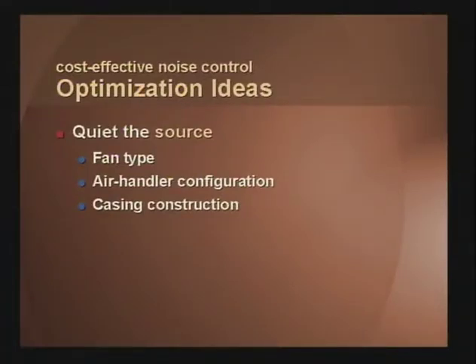Let's take a look now briefly at the source. The source is the air handler. What can you do there? Well, solutions fall in one of three categories. Take a look at the fan type selection. Take a look at the air handler configuration. Once you pick the fan, can you reconfigure the air handler to take advantage of stacking and turns and multiple discharges? And then finally, look at the unit casing. And is there anything you need to do to the casing to enhance its acoustical reduction of noise at the source?